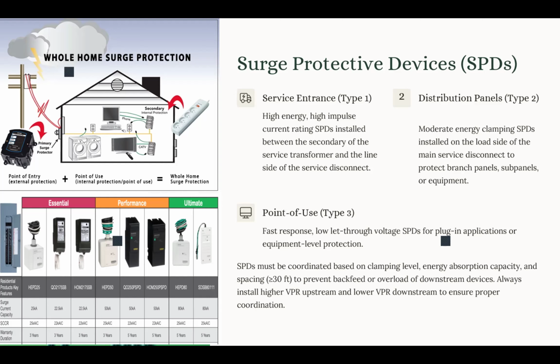Now we have type 2, which is the distribution panel. It is inside our panel boards. It's a moderate energy clamping, and basically it protects branches in the panels. And we have type 3, which is point of use. These are connected either at the point of connection of each equipment or inside the equipment, so they can control low energy voltage spikes and surges.